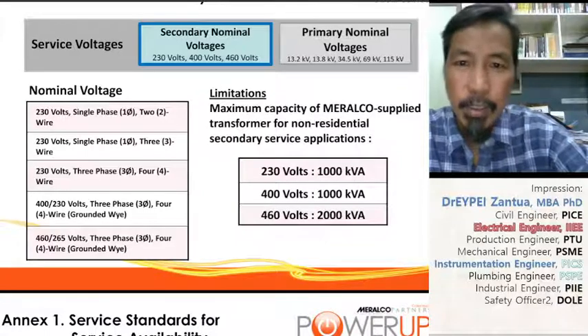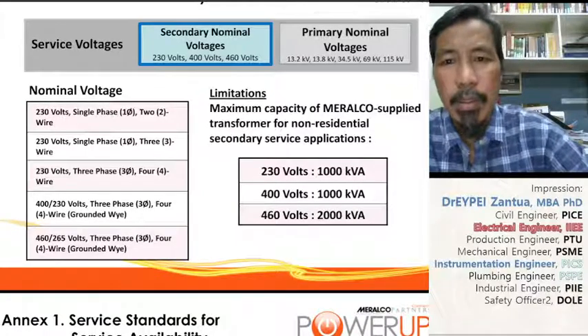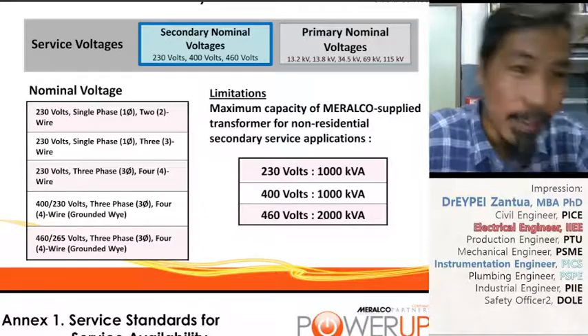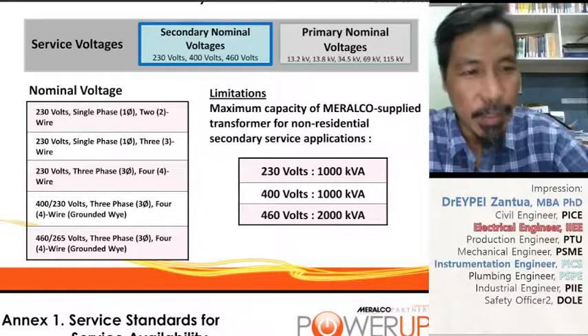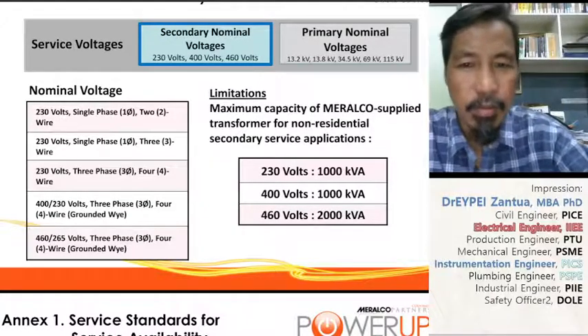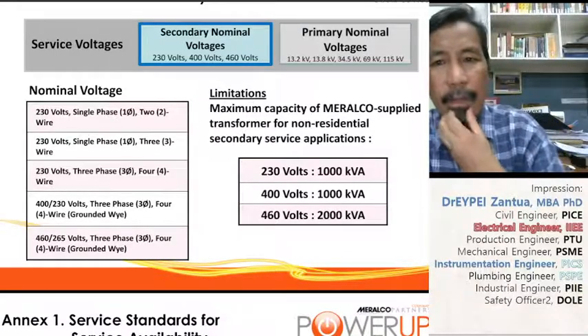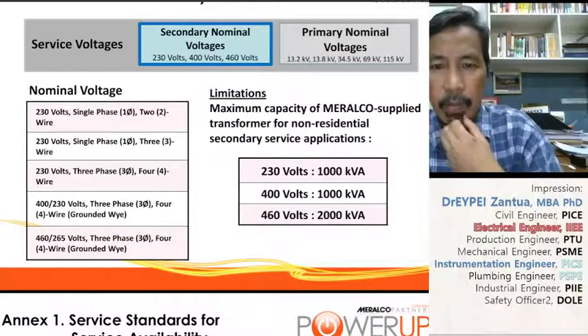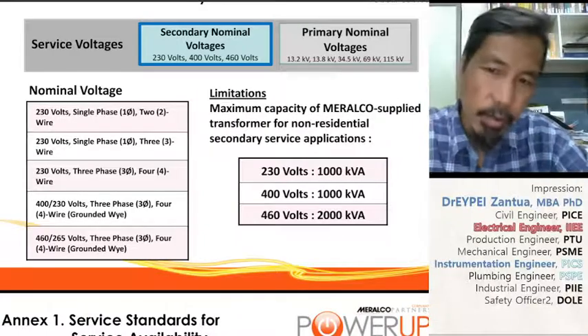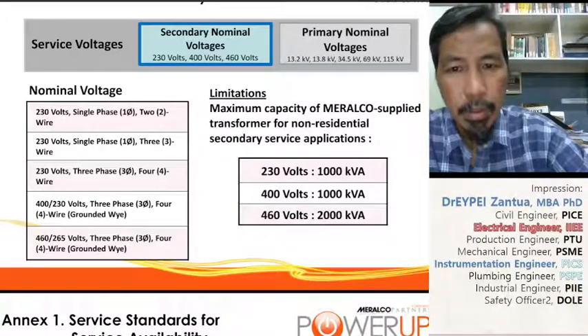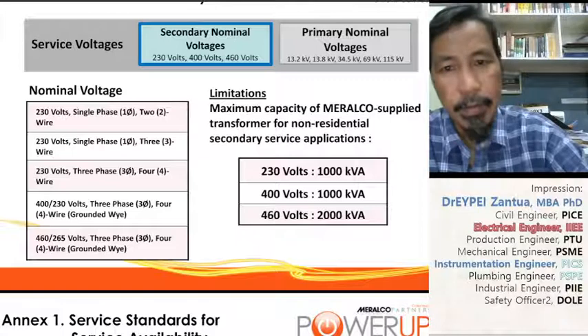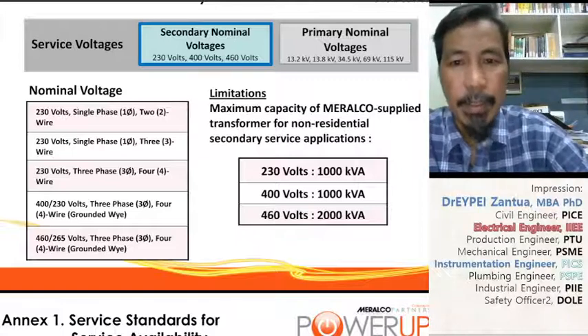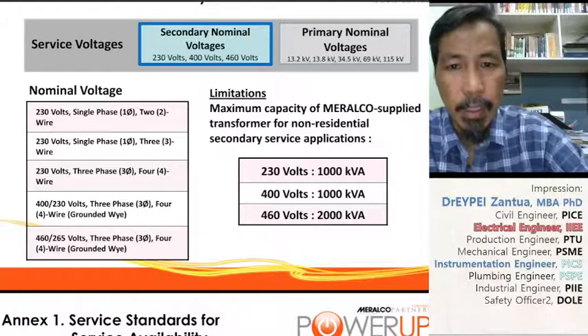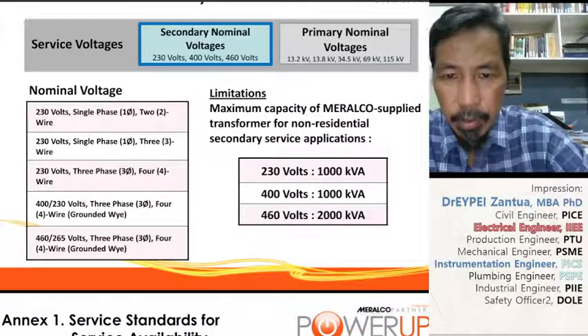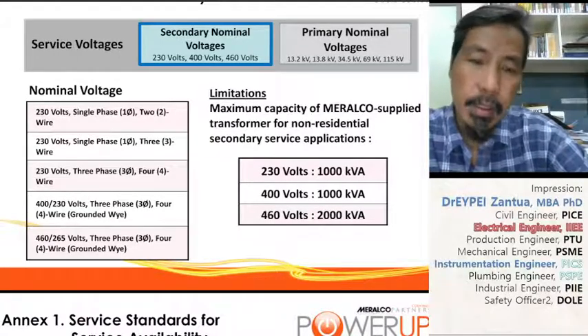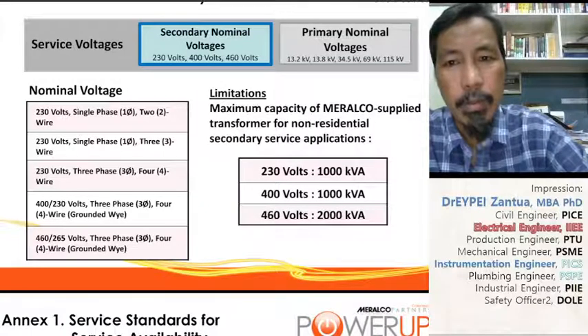Limitation. Maximum capacity of Meralco supplied transformer for non-residential. Okay, again, non-residential. This is businesses: commercial, institutional, and industrial. Okay. Secondary service application, 230 volts is up to 1000 kVA or 1 megavolt ampere. 400 volts, 1 MVA. 460 volts, 2 MVA. So, these are maximum limitations.